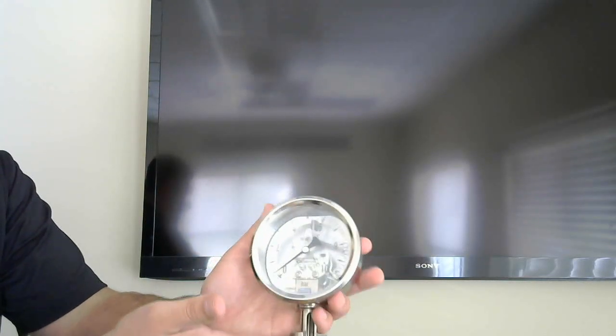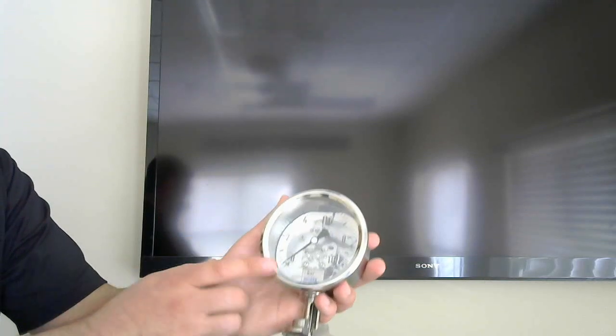Also, when this gauge's diaphragm is ruptured, it immediately goes to reading 0 and stays at 0. That's great because you have an immediate visualization that the gauge is not working and that you need to change it.